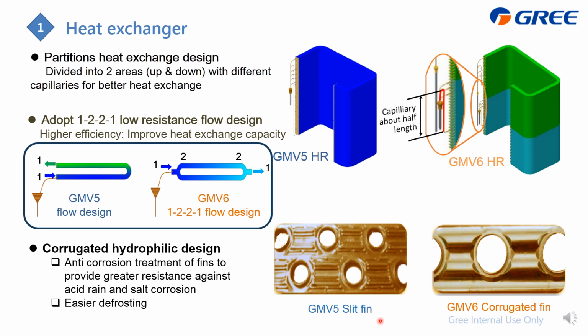However, in heating mode, the outdoor heat exchanger will generate condensing water in low temperature situations. It will become ice, which means the ice will stick on the surface of the fin. And if there is a lot of slit here, when we do the defrost, which will make the ice become water, the water will not flow out easily because it will just stick on this slit. And then next time when it is going back to heating, this will cool down again and become ice easily, which means for heating performance, slit fin is not that good.